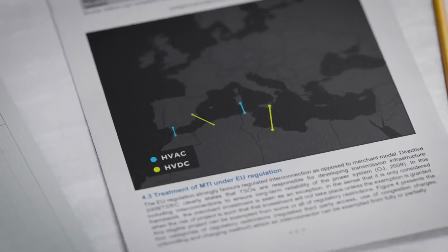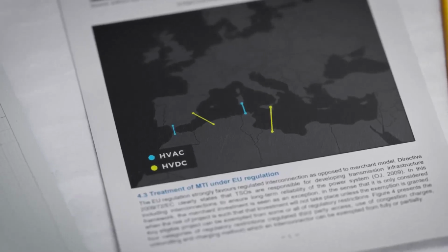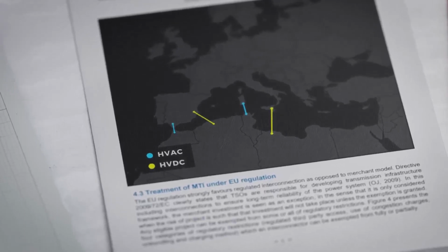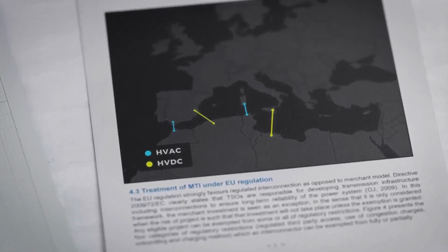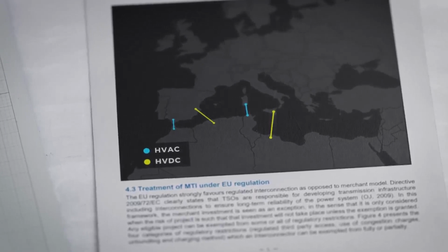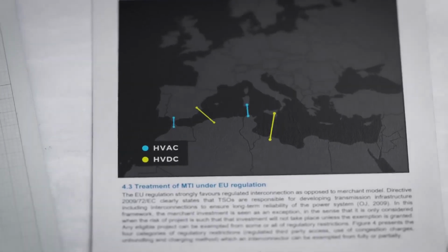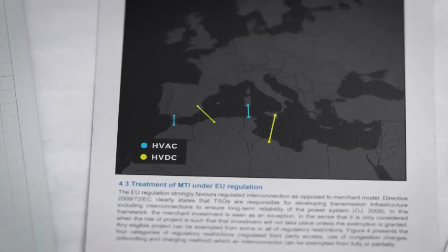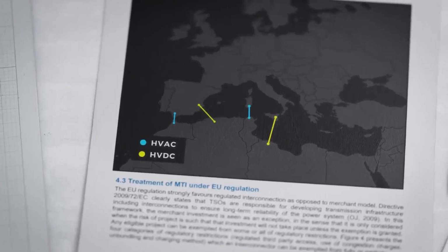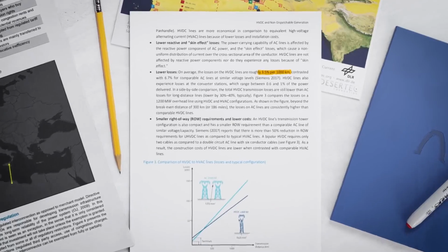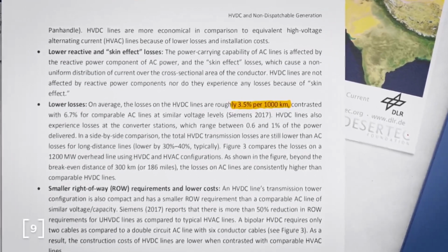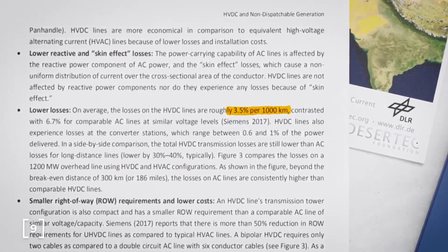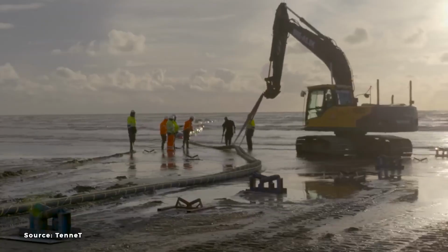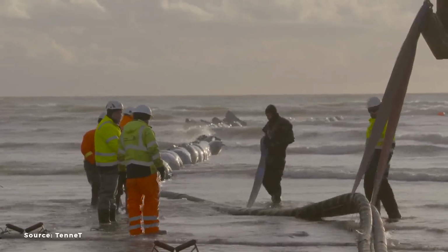So lines connecting Morocco directly to Spain, which spans only 28 kilometers, don't make sense for high-voltage DC, while longer lines connecting Tunisia to Italy will likely be high-voltage direct current lines. Transmission losses for high-voltage direct current are about 3% per 1,000 kilometers, and Germany's capital is only 1,800 kilometers from Tunisia. Transmitting power with this much investment money is perfectly feasible.